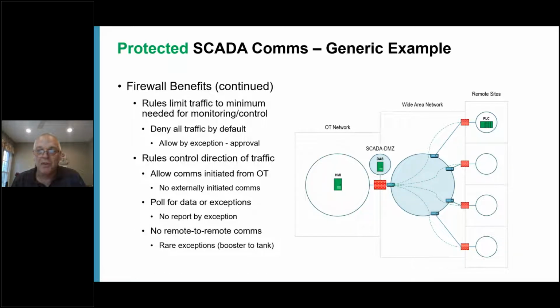So what we could do with that protocol is poll for exceptions. We'd have this server say, site one, do you have anything that changed? It may say no, go to the next one. So it goes to the next site. Site two, do you have anything that changed? Yes, I have some things that changed, here it is, and it would respond back. That's one way around the report-by-exception capabilities of some communication protocols.